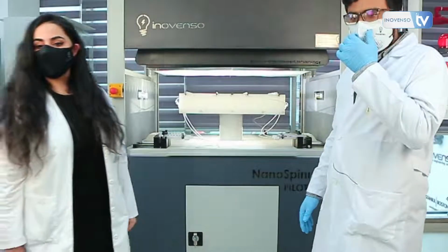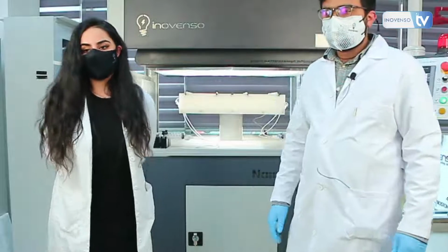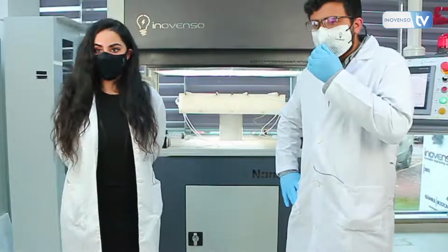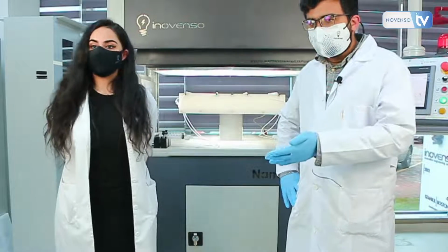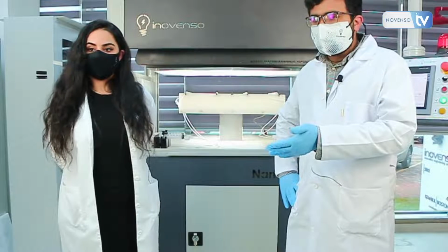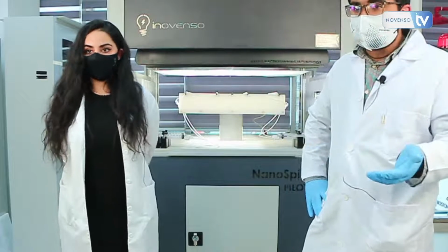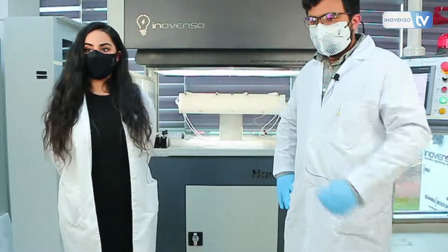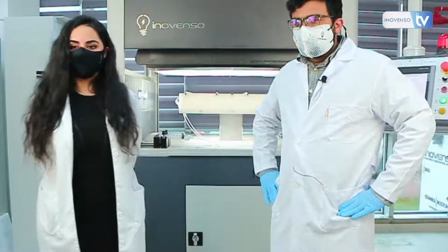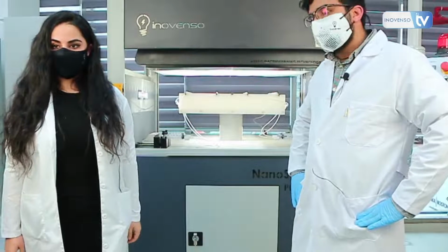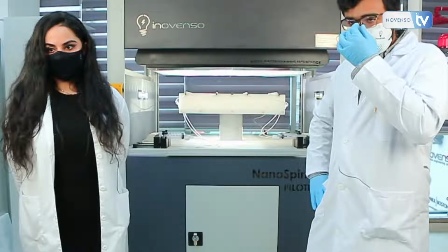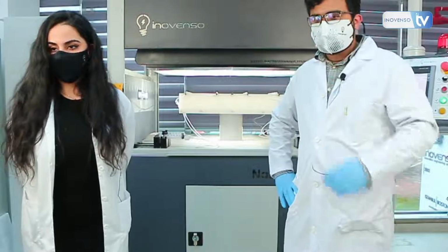So we have another question. What is the substrate used in HEPA producing filter? Okay, so there are many filters being used. There can be spun bond. There can be silica glass fibers. In certain cases, there are also cellulose filter materials too. So it's actually a broad answer. There are several types that we can use. But for our purpose, we showed you the substrate of polyethylene terephthalate, which can be used as well for air filters.